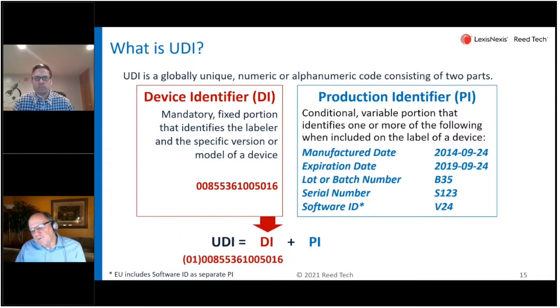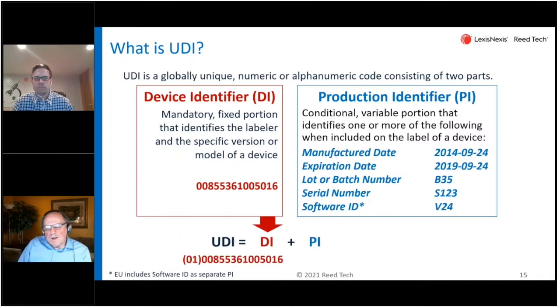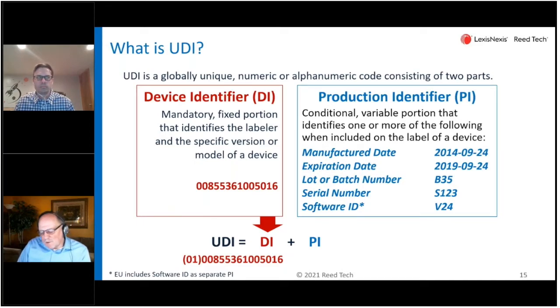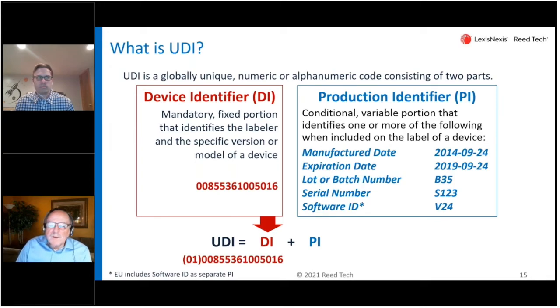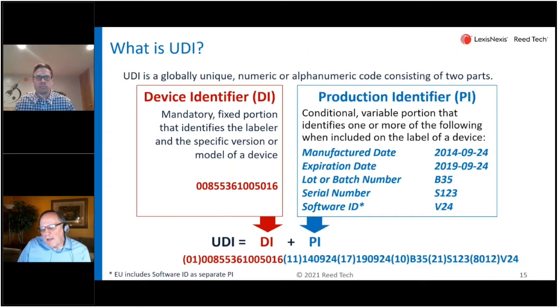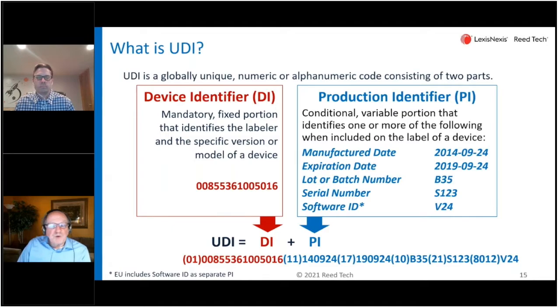Using GS1 as an example here, the device identifier has a long string of numbers. There's a code at the beginning — parentheses 01 — that indicates the following numbers are a device identifier. In the same fashion, any or all of those production identifiers are added to the full string of a UDI, so it gets quite long.